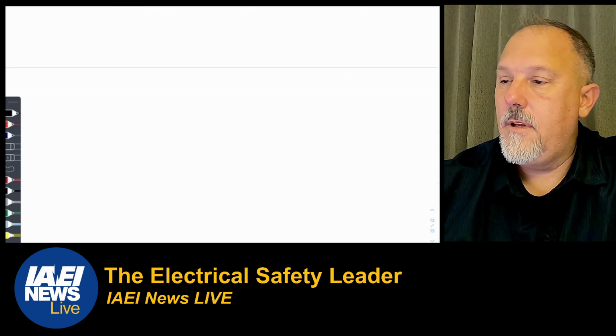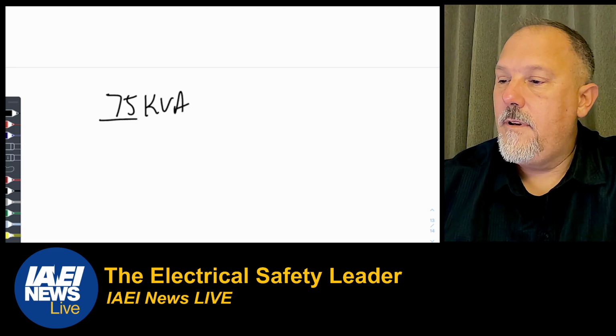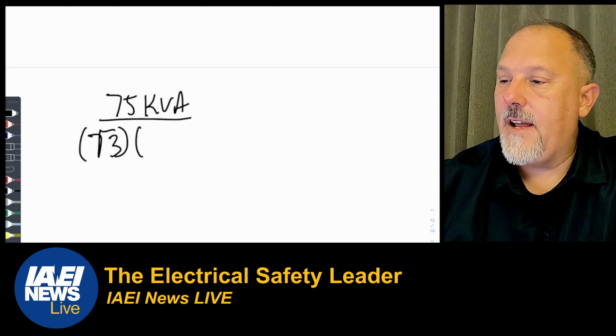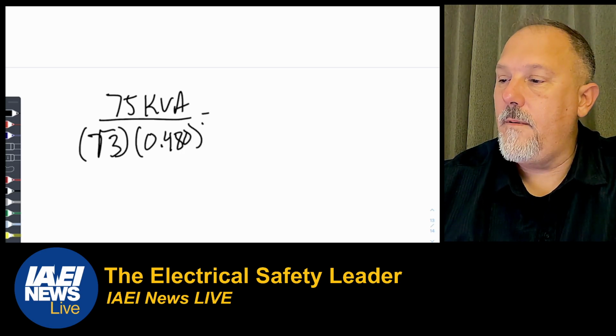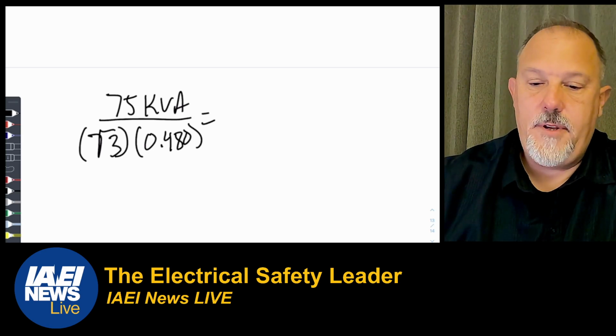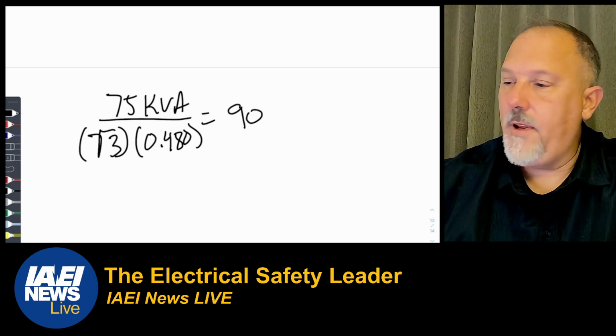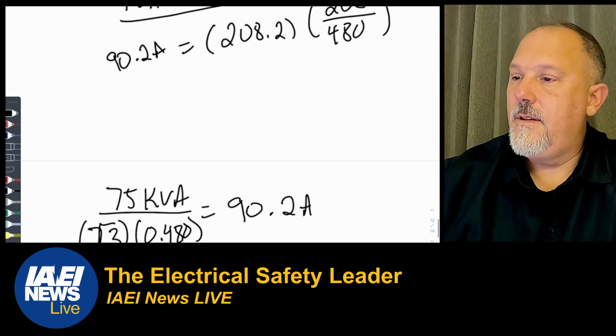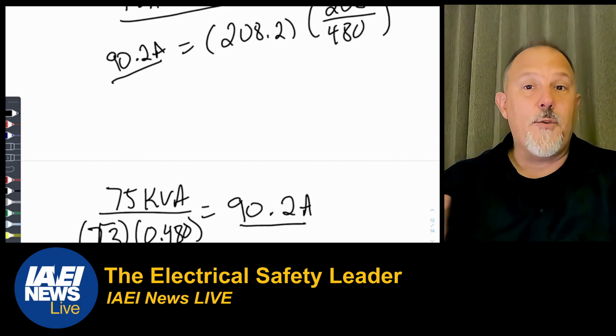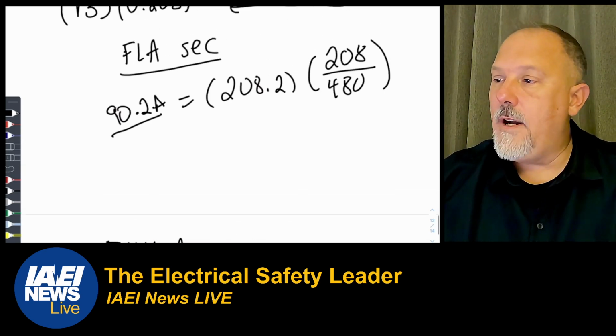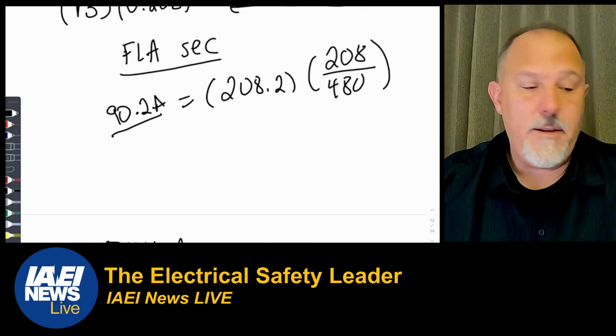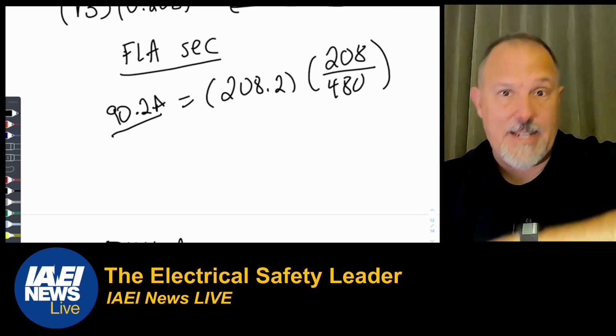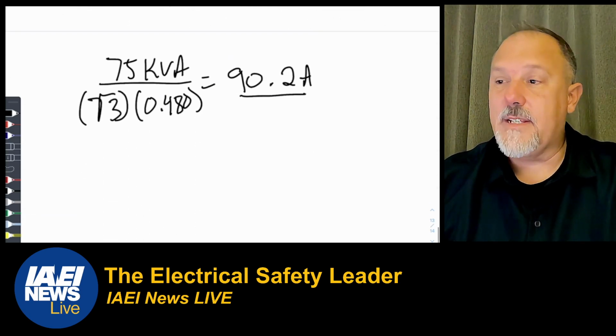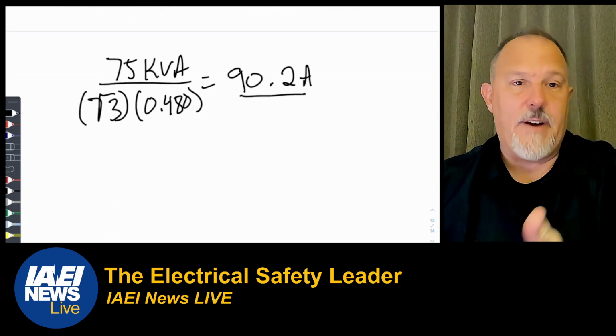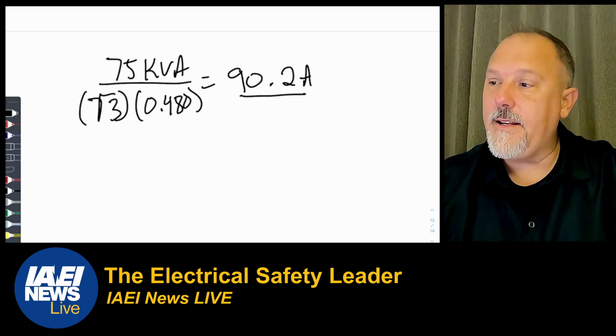75 kVA divided by the square root of 3 divided by 0.480 is 75, 3 square root, 0.48, 90.2 amps. Two different ways to get to the same number. One, I just used the turns ratio, 208 over 480 of the transformer, to reflect the secondary current to the primary, and I got 90.2. The second way is to do the standard equation: take the kVA divided by the square root of 3 divided by the kV, and I get 90.2 amps.